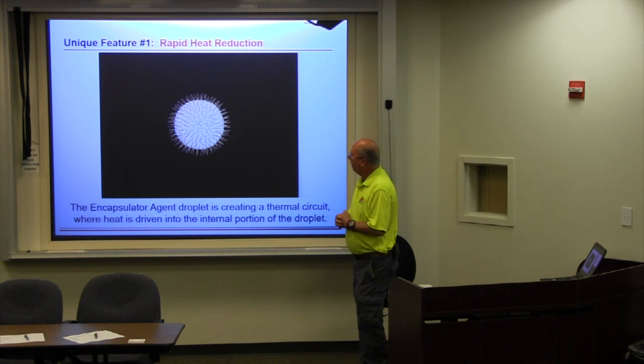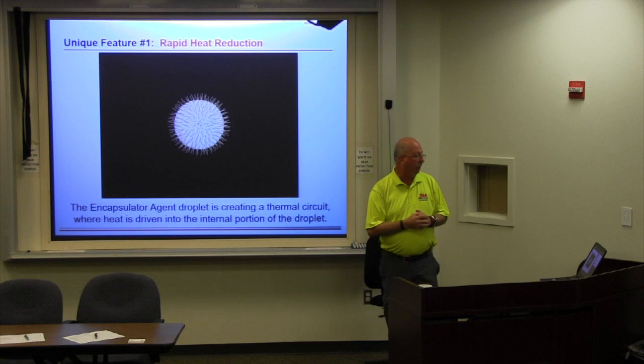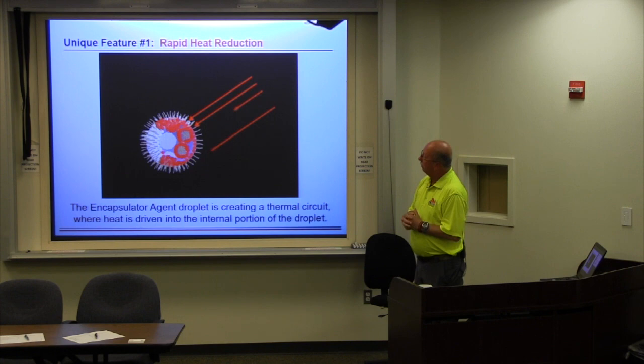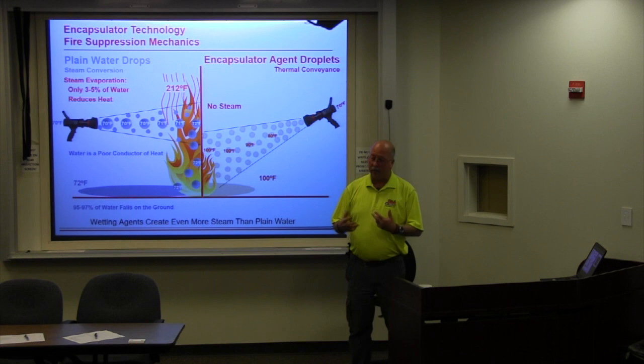Okay, so what happens is as we sit there and we are used in these types of applications, fire, whatever the application may be, you've got this water molecule, you got these little fingers that act like heat sinks. So now what they're doing is they're drawing the heat internally into that water molecule where you have more micelles. So what you've done is you've taken a water droplet that was maybe 10% effective at cooling, and you've now made it 90% effective at cooling. So that's where that rapid cooling is going to come into play. So because of that, you're going to need a lot less water.